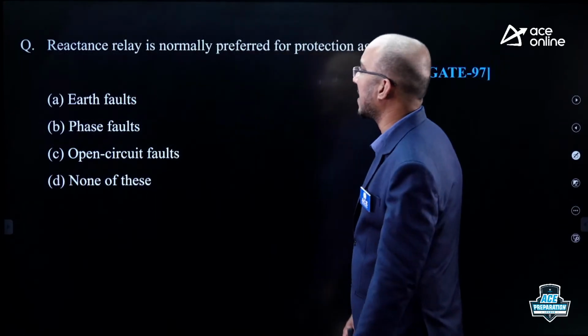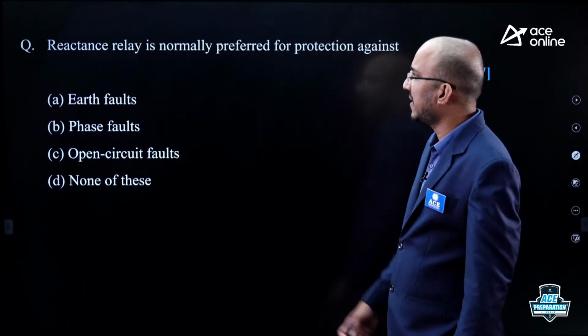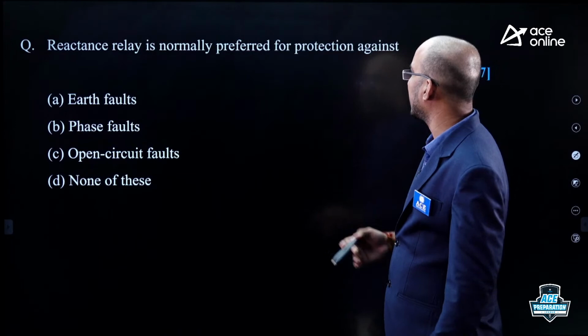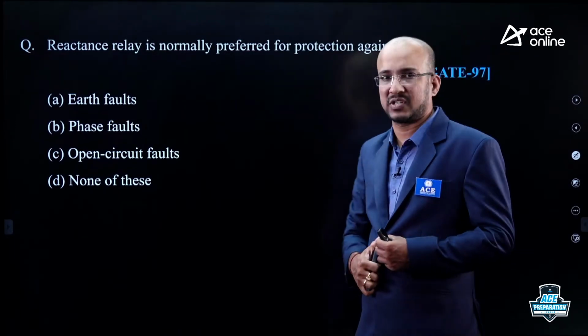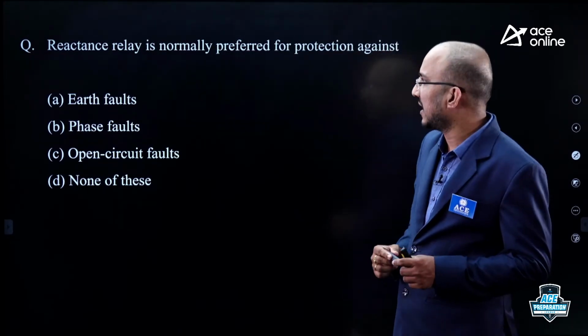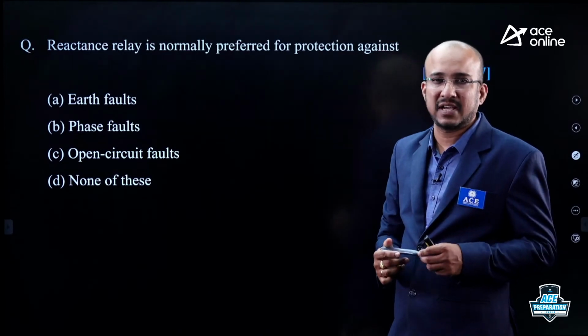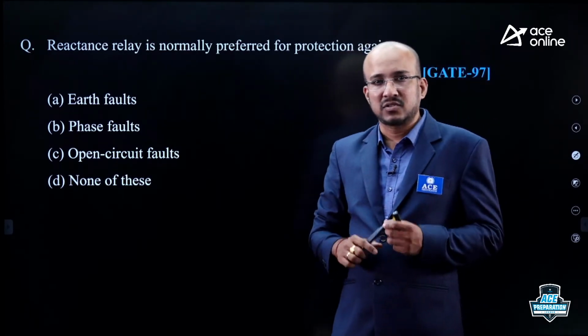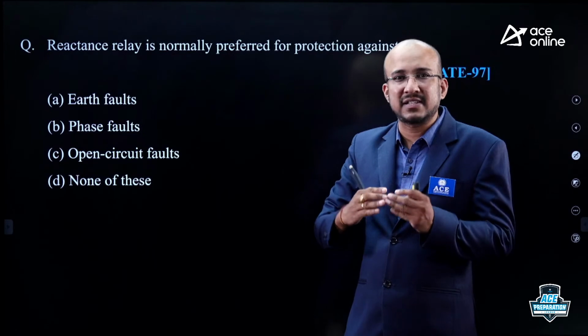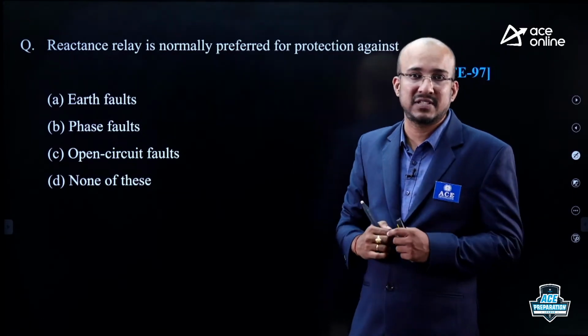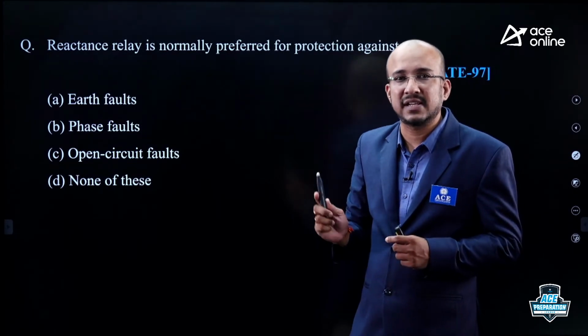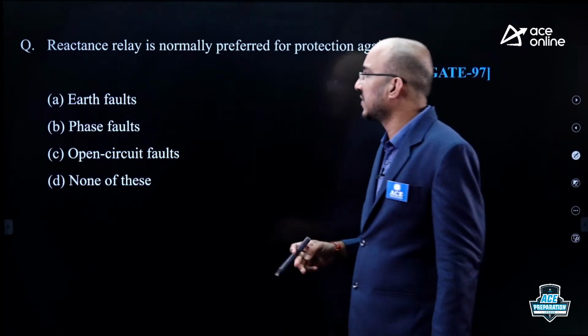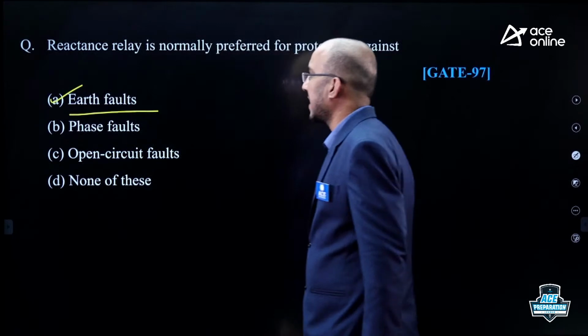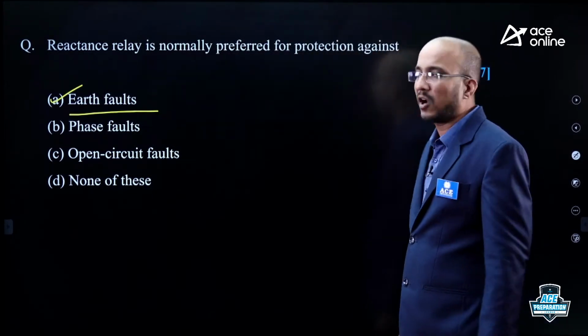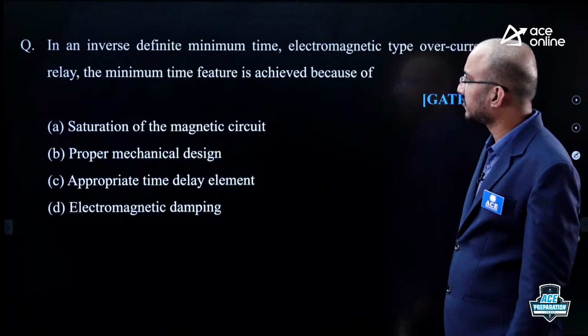Now let us observe here. This is a question from distance protection. Reactance relay is normally preferred for protection against what? Where do you use the reactance relay? As we have discussed in class, the operation of reactance relay is independent of resistance phasor. That is why it is preferred for earth fault protection. Reactance relay is used in earth fault protection.